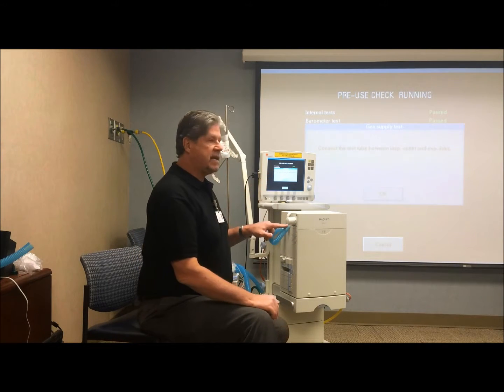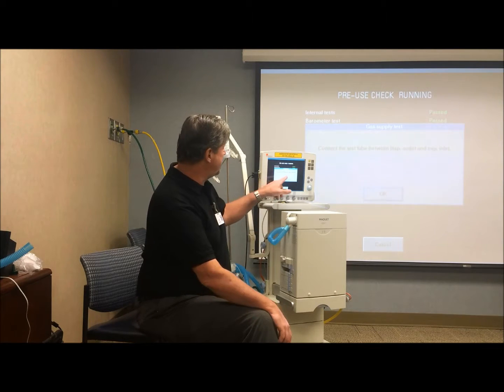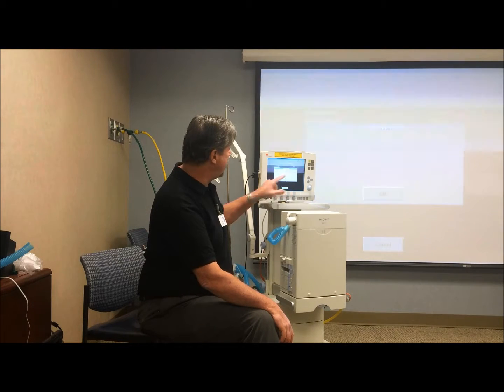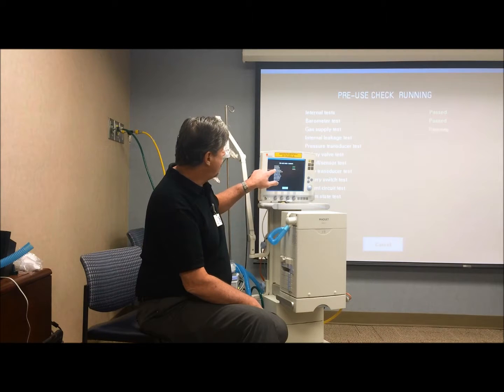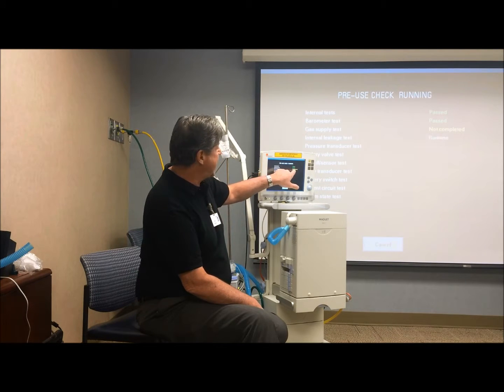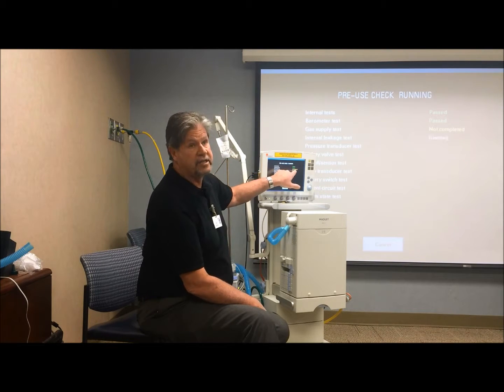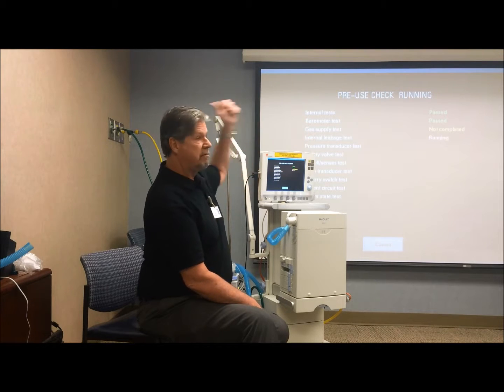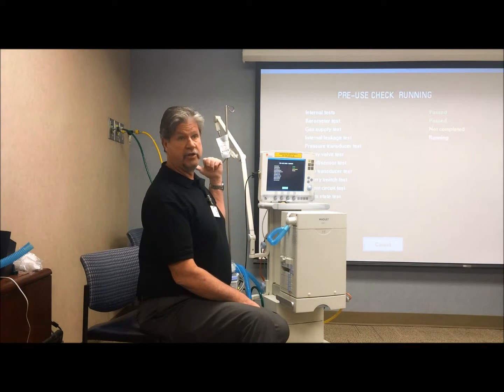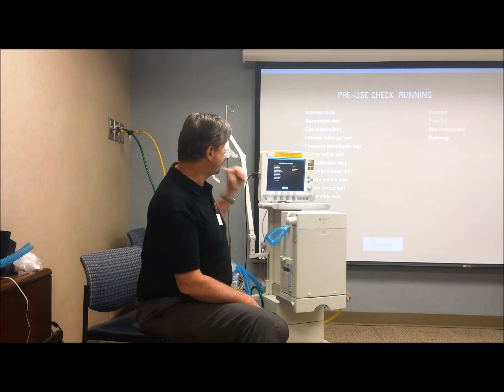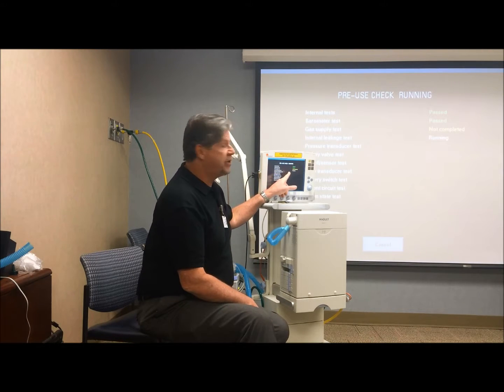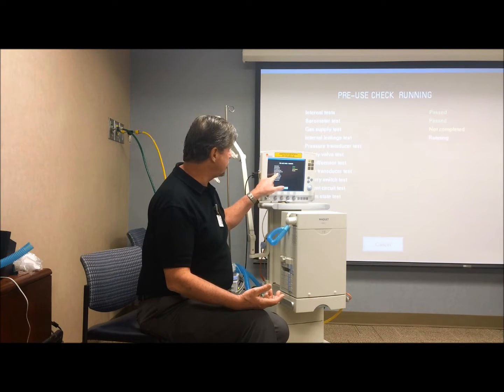So we connect the test tube between the inspiratory and expiratory outlet, and then say OK. And the first error that I'm going to get is not a failure, but it just says not completed, because I don't have any air going in, just O2, because the air is turned off. But it can still do an internal leakage test. It can do a pressure transducer test.